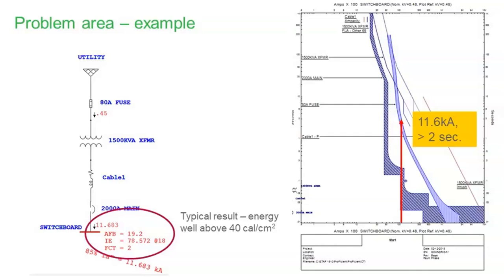How do we get there? You look over on the right-hand side, I've got 11.68 kA, 11,680 amps of arcing fault current. If I have an arc flash event there at that switchboard, you follow the red arrow up to the fuse curve, and they intersect beyond 2 seconds. We cut calculations off at 2 seconds to get the 78 calories. Okay, that's high. I already told you service entrance equipment would be a potential problem, so why am I showing you this?